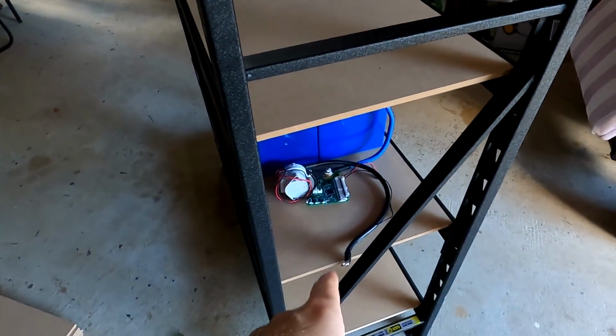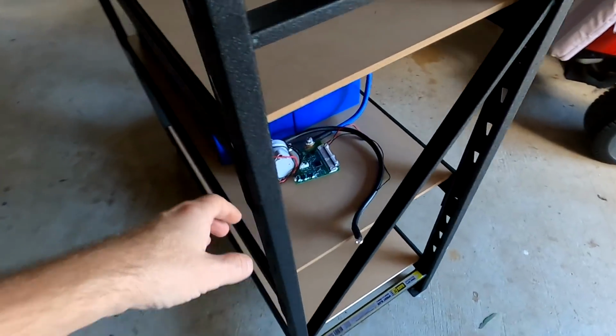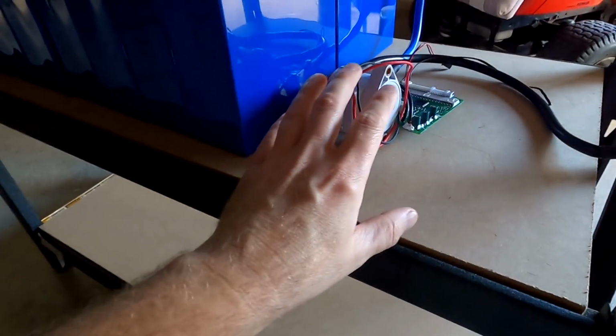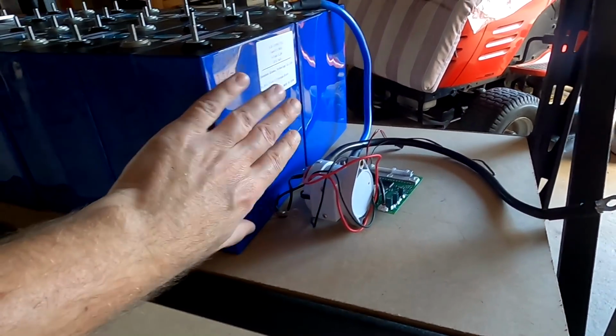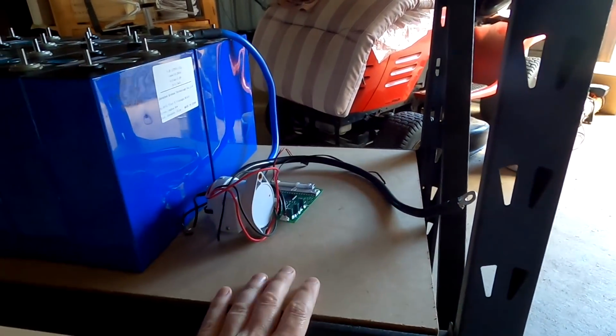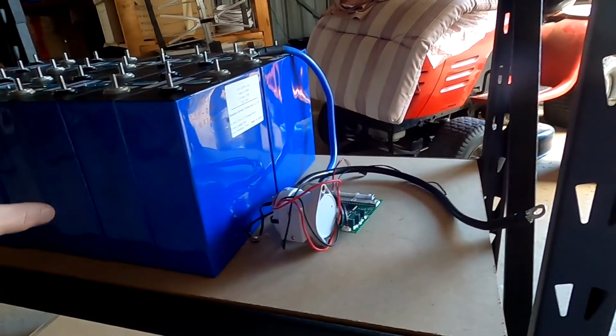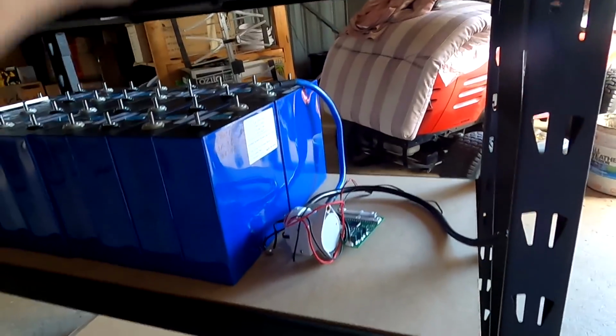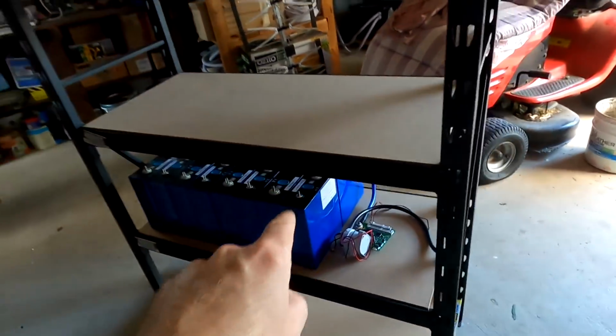So I can take one full length of 4 meters of bus bar, which I need to purchase apparently, to connect all our batteries. This is my preferred solution at the moment - to use a bus bar in here, positive, negative, and then connect our main switch and main circuit breaker or fuse to the battery, to the bus bar. I can isolate them and have one battery bank completely off, while the other two are still operational.